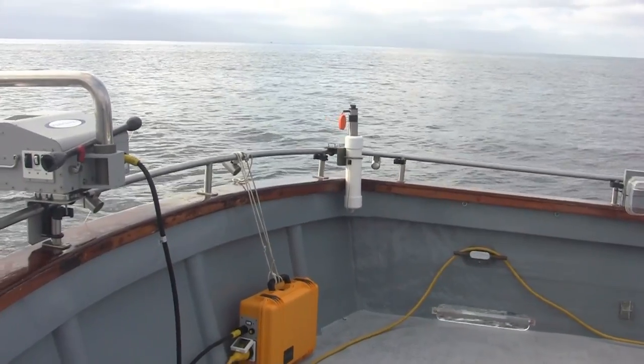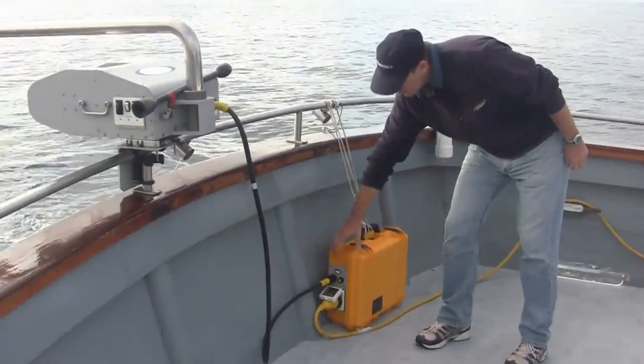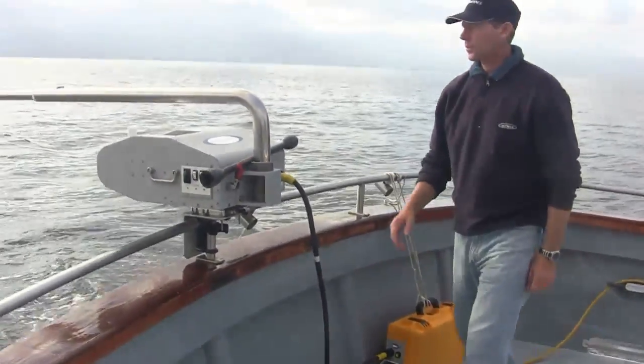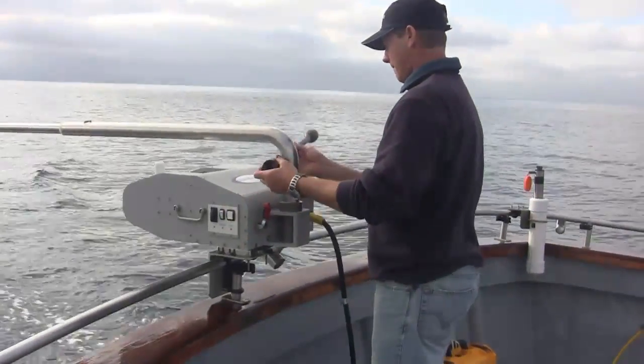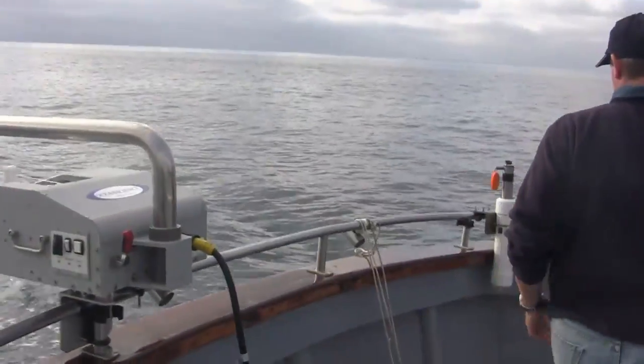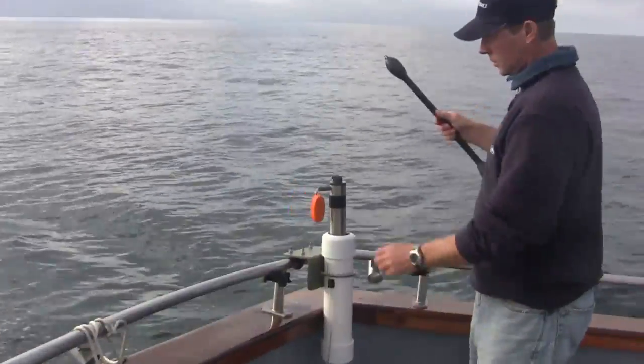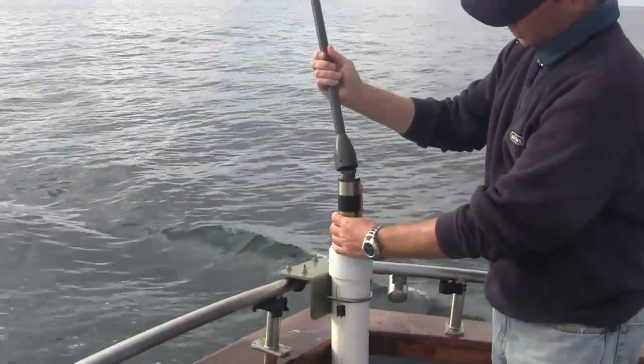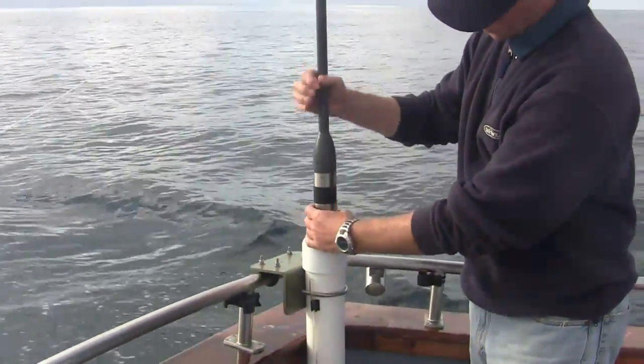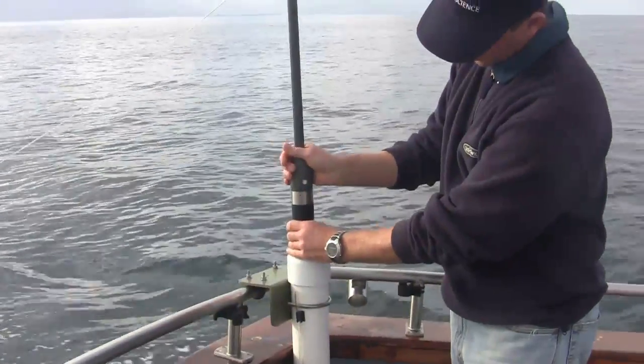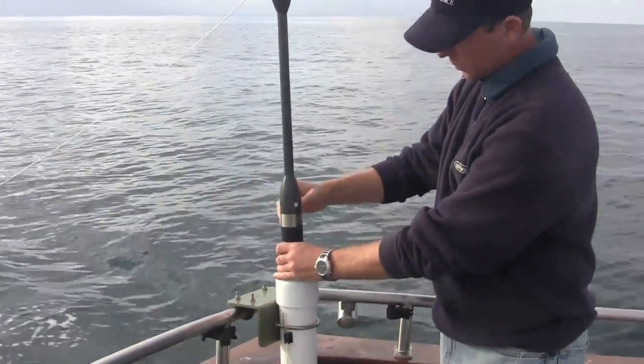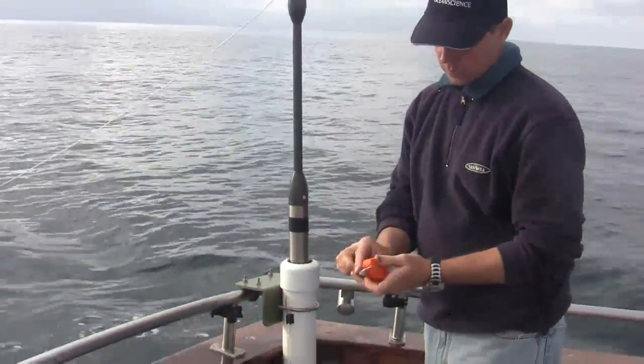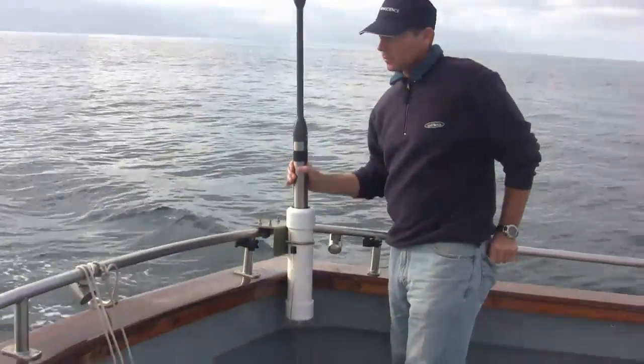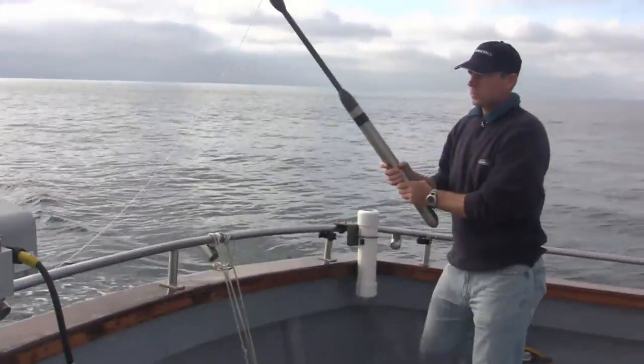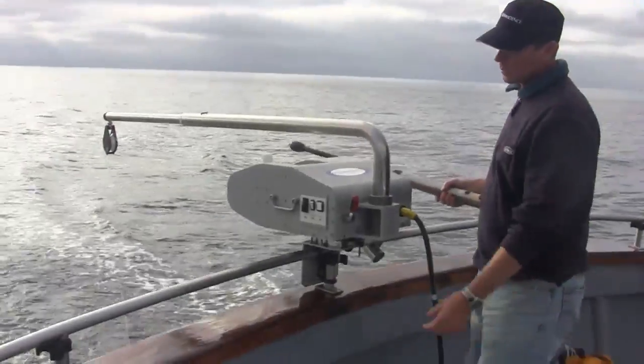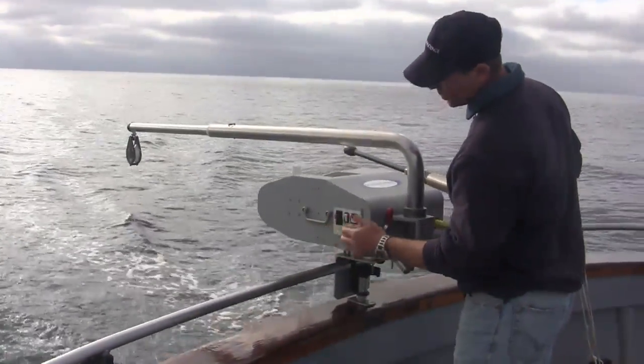So far all the deployments we've shown have line on the tail spool. This time we've got a winch only, no rewinder, and this probe is being deployed in tow-yo mode with no line on the tail spool. This is a sound velocity probe. Quite often the sound velocity probe is used in this fashion. It drops quickly, so you can achieve typical survey speeds up to about 8 knots, 400 meters without even rewinding. So it makes it a simple way to deploy the probe.